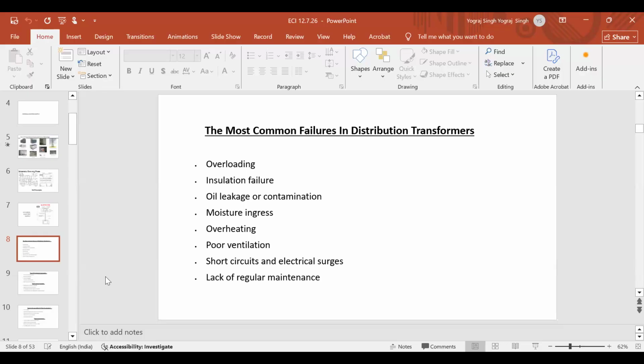Now oil leakage or contamination. Oil is providing two services. One is it is providing the insulation. Second, it is also providing heat dissipation. So if the oil is leaking, then the level of oil in the transformer will come down, so the heat carrying capacity will reduce. Moisture ingress: it is clear that the transformer should be airtight. It should not allow any moisture to enter inside. There is always a silica gel bottle provided over there, which gives an indication whether the transformer has received some moisture, or the oil has got a higher level of moisture.